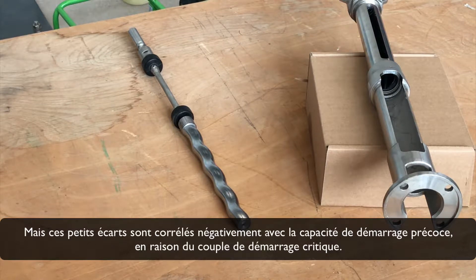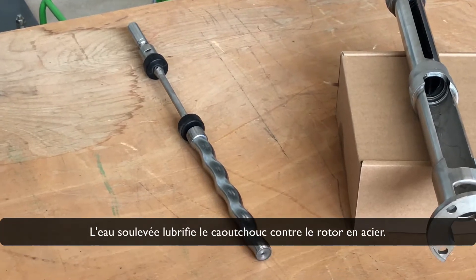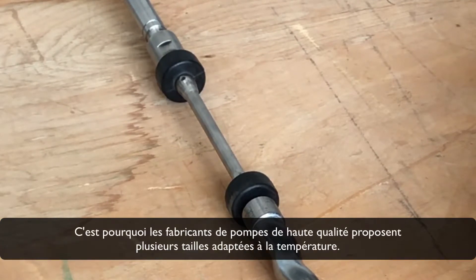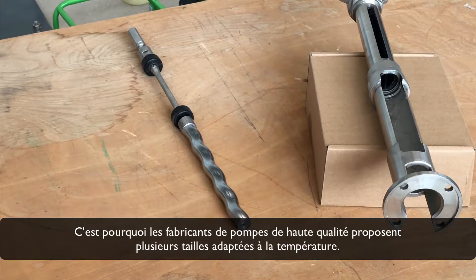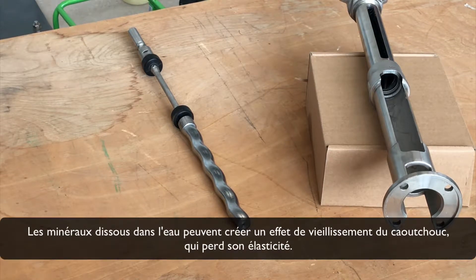These small gaps are negatively correlated with early start-up ability due to the critical starting torque. The lifted water lubricates the rubber against the steel rotor. Warm water causes expansion of the rubber, which is why manufacturers of high-quality pumps offer several temperature-adapted sizes — tolerances differing in this case only by millimeters. Dissolved minerals in the water can create an aging effect on the rubber, causing it to lose its elasticity.